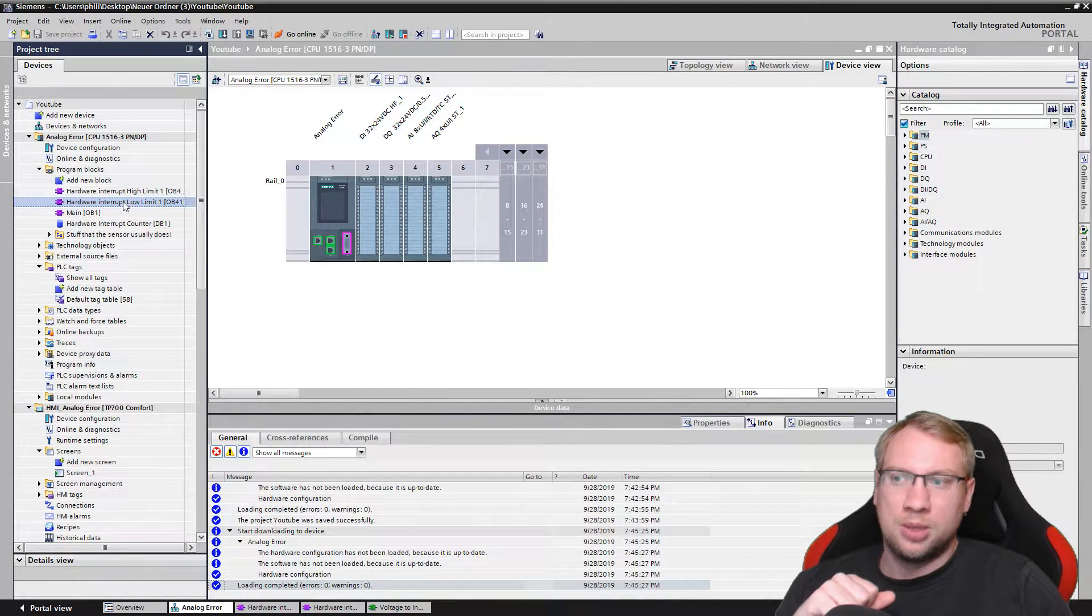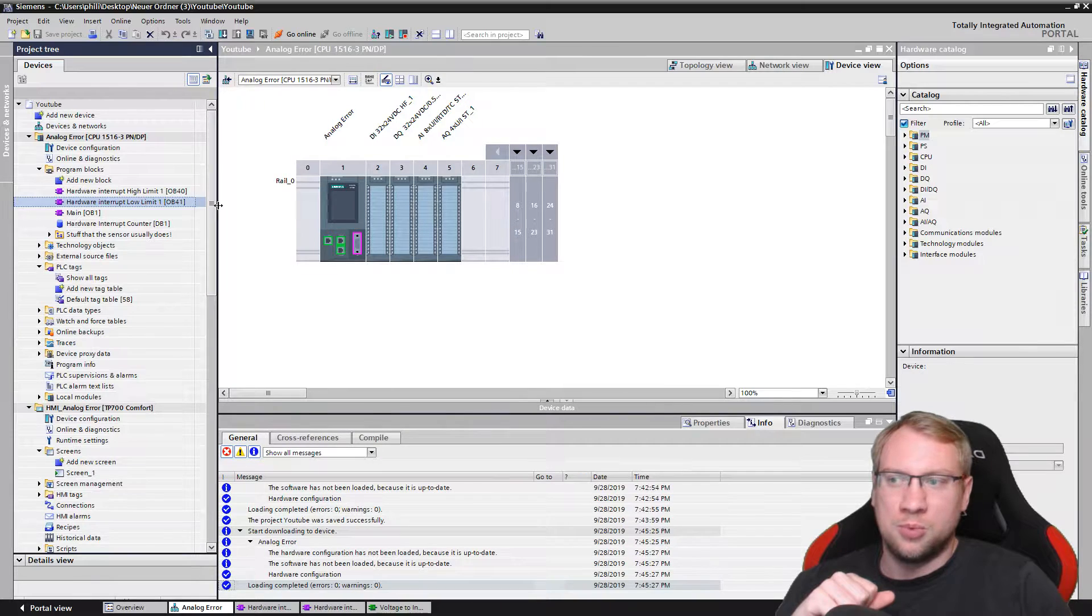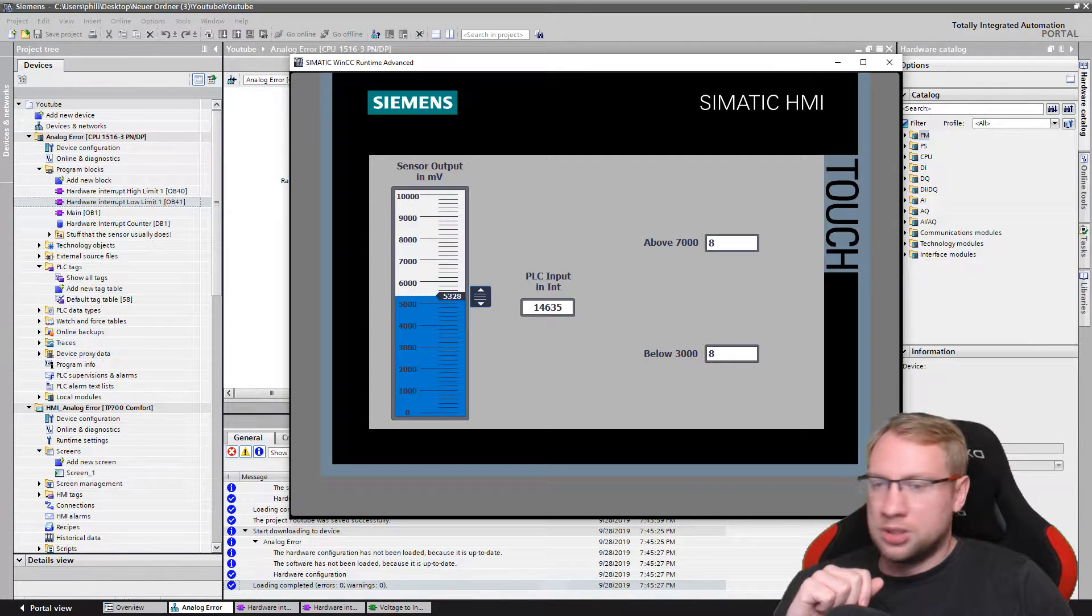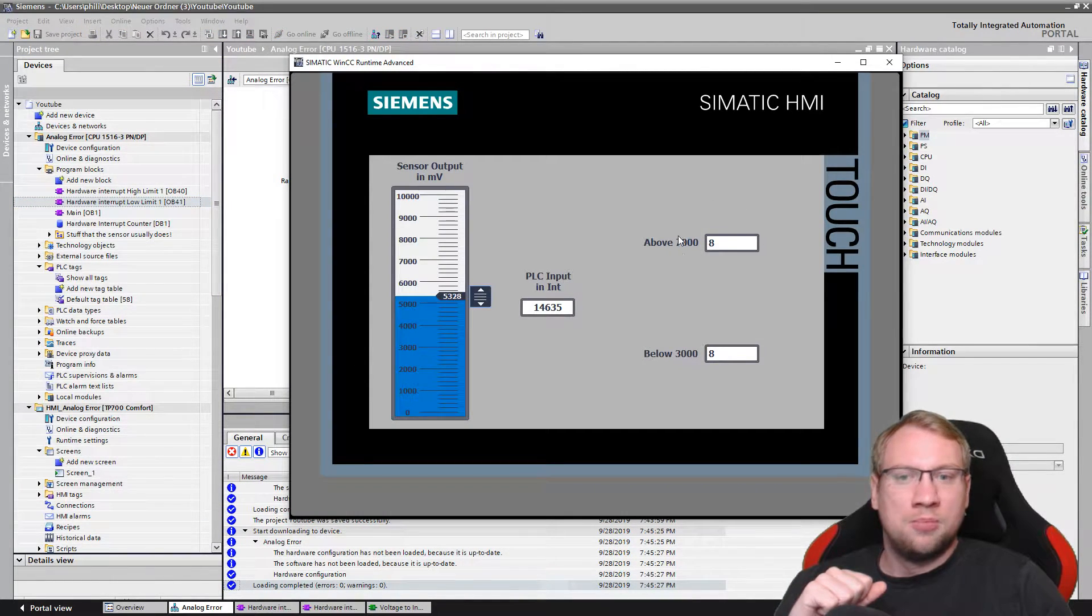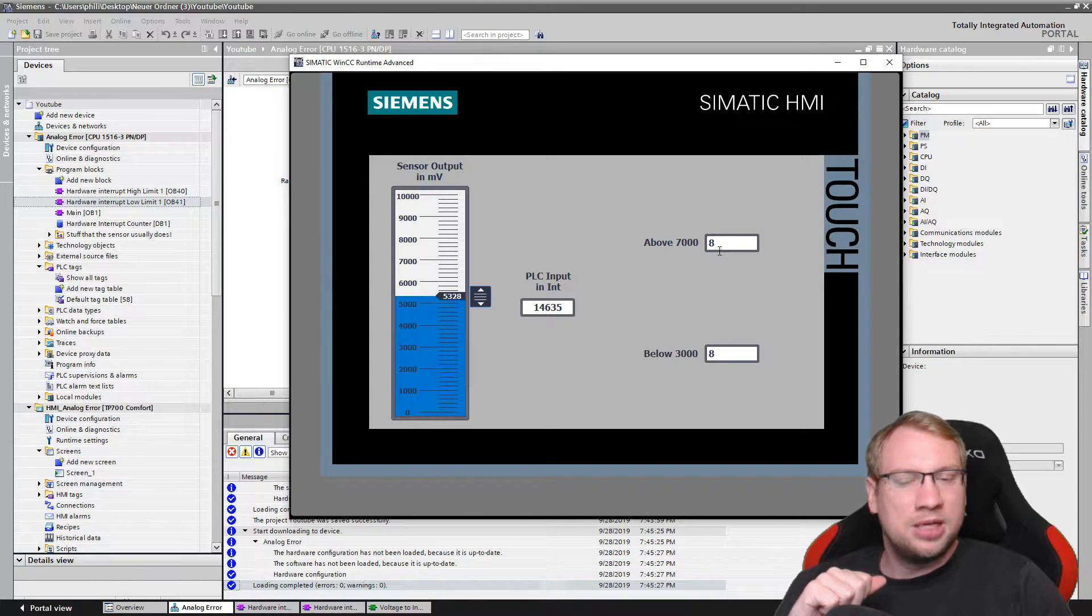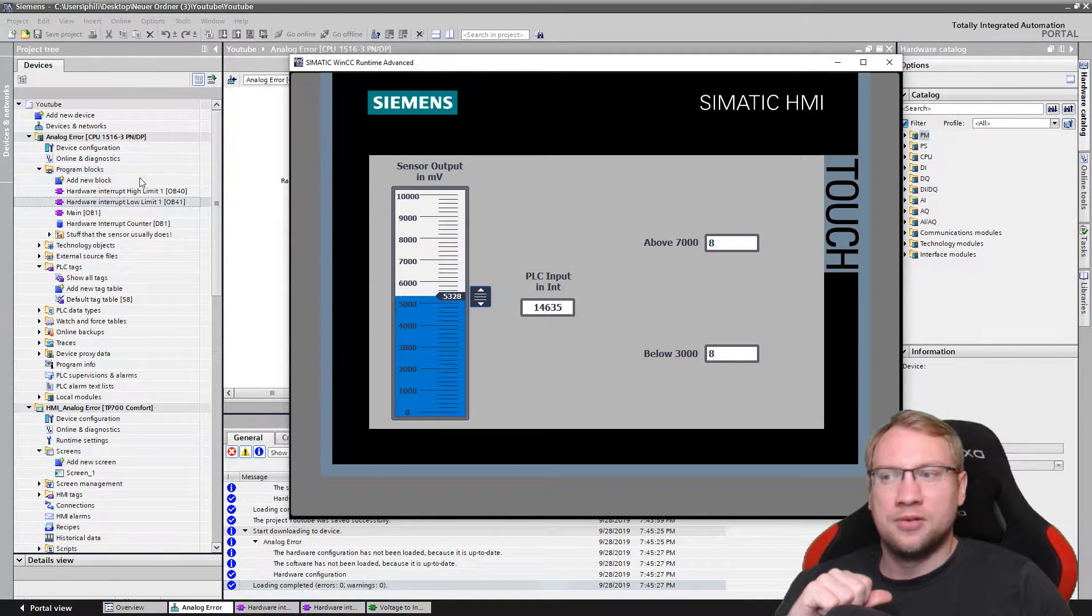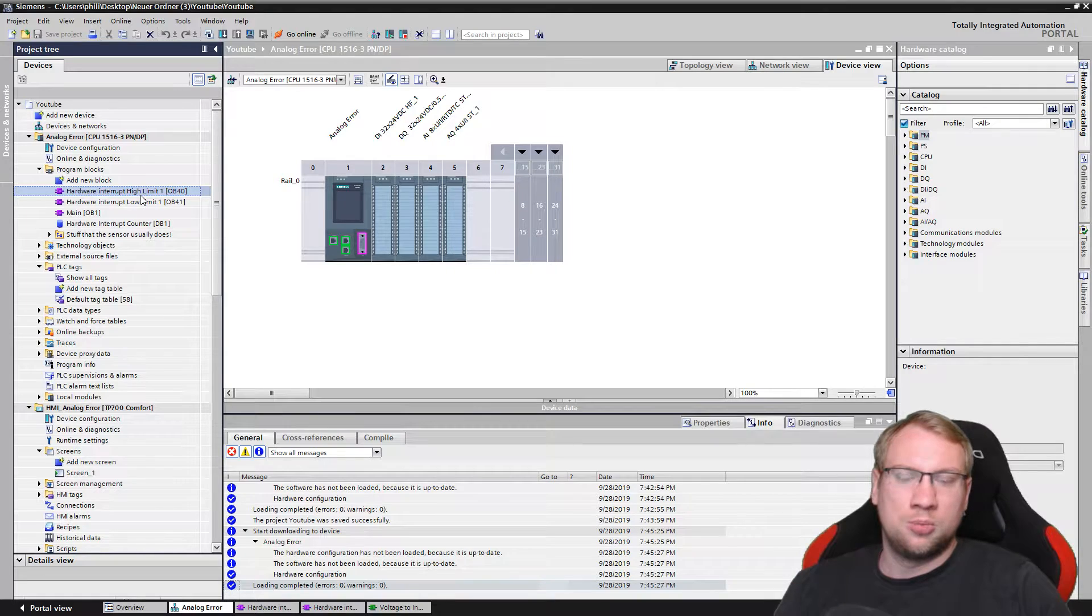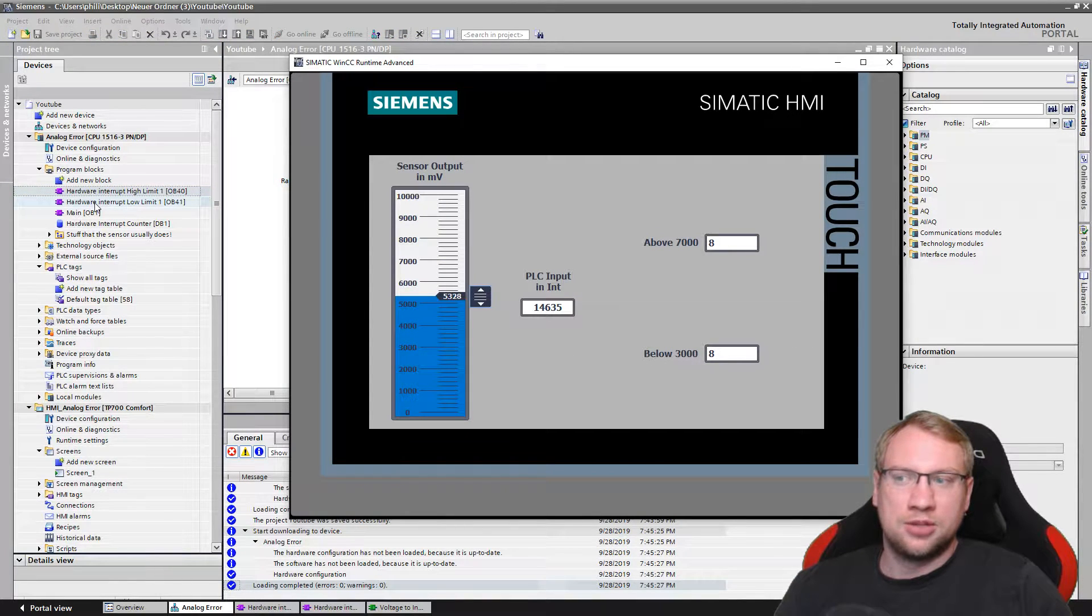It works as follows: if I go above 7,000 millivolts I will have this function executed, this OB. If I go below 3,000 I will execute this function, which is just a counter in both.